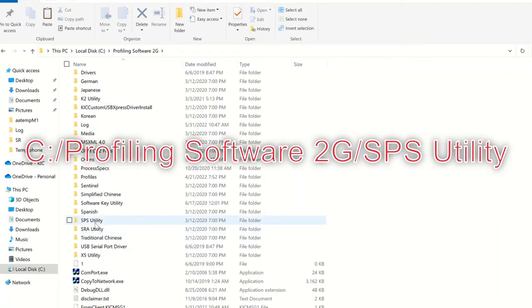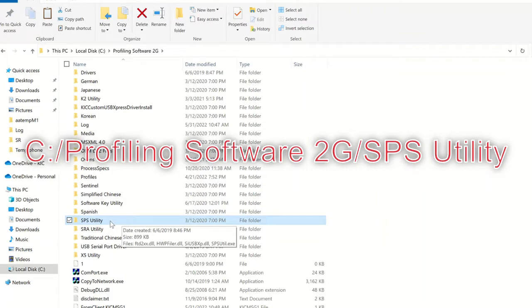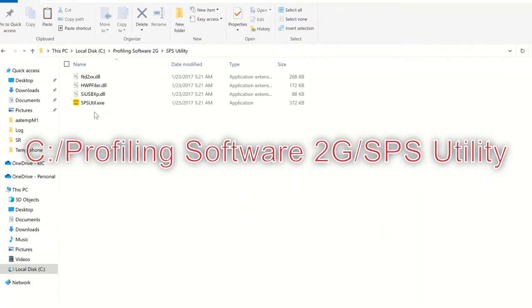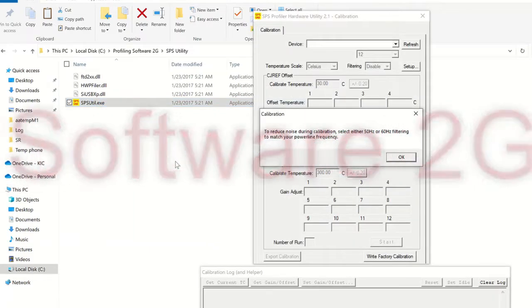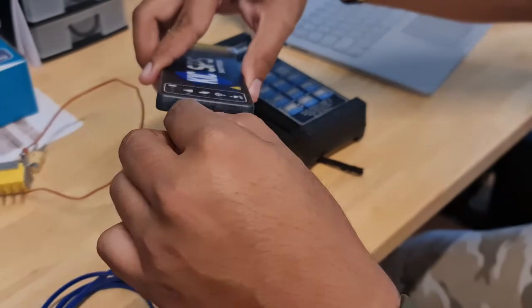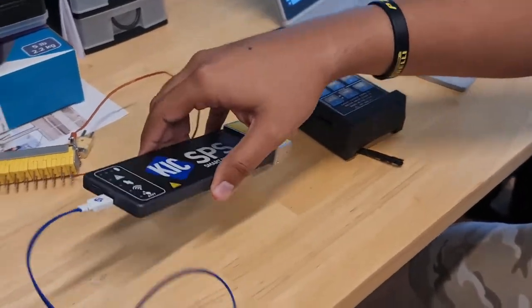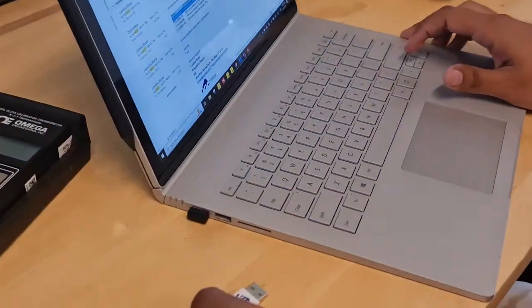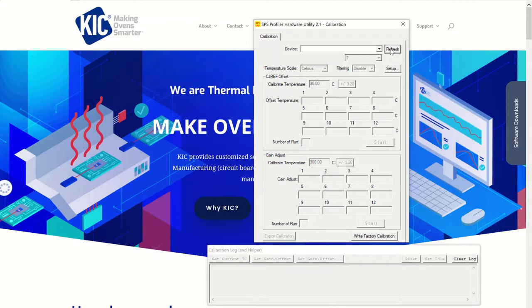Once you have located the SPS software utility, double-click on the software utility icon to launch the application. When the SPS utility launches, you should see two windows open as shown in this video. When you see the pop-up window message for the frequency filter, just click OK. Next, turn on and connect the SPS profiler to the PC via the USB cable. Then click on the refresh button as shown in this video to make sure the profiler is correctly displayed.